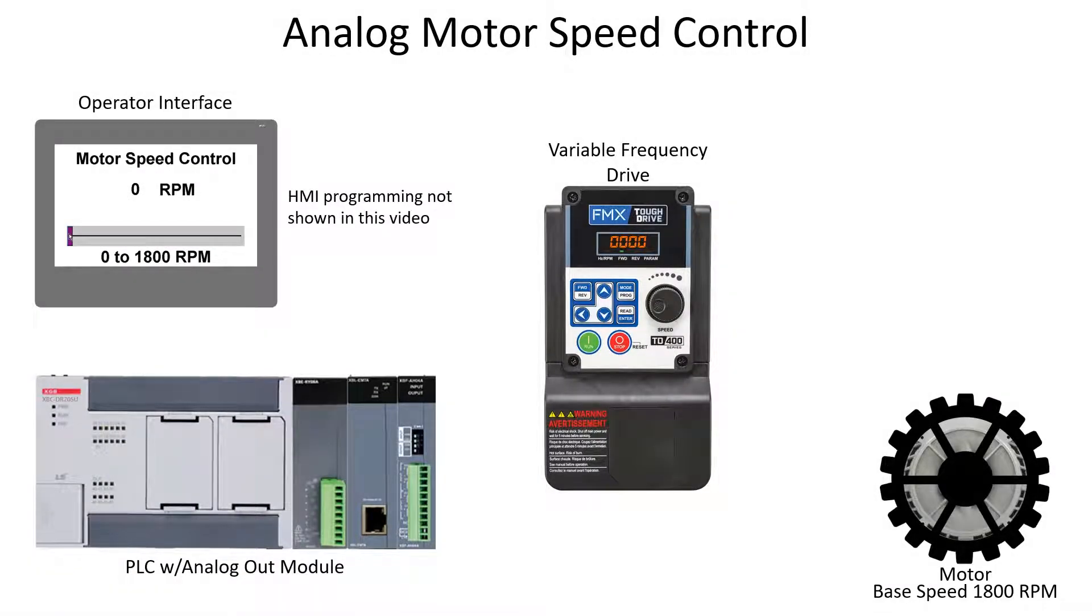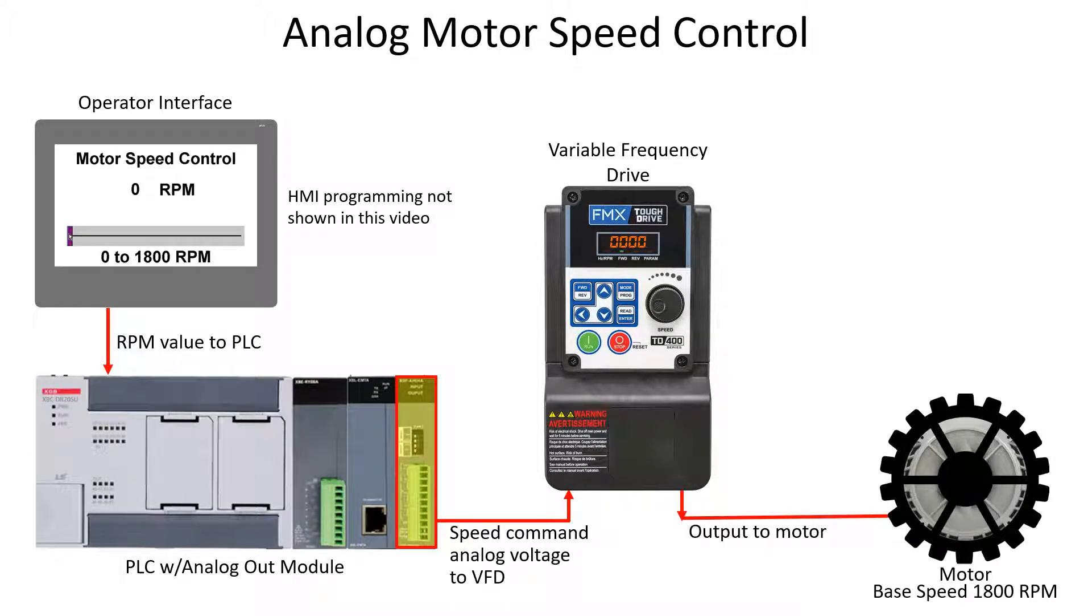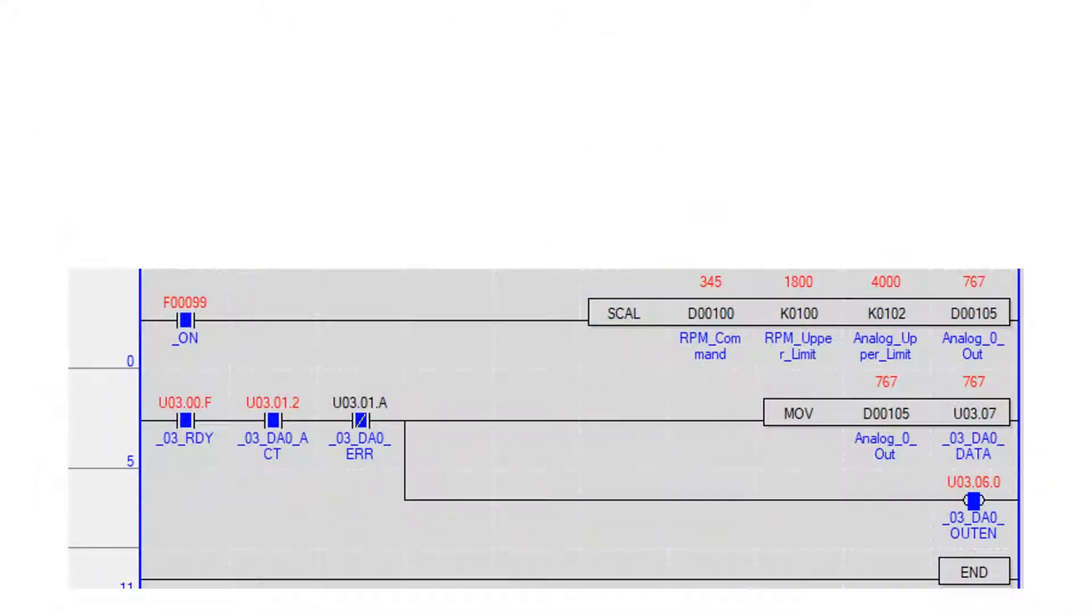The system shown uses an operator interface to input motor speed to the PLC. The PLC is configured with an analog output module. The analog output is connected to the analog input on the variable frequency drive. The VFD is configured for an RPM range of 0 to the base speed of the motor. In this example, 1800 RPM is the base motor speed. We will now build a program in the PLC to scale and output analog voltage to the VFD.